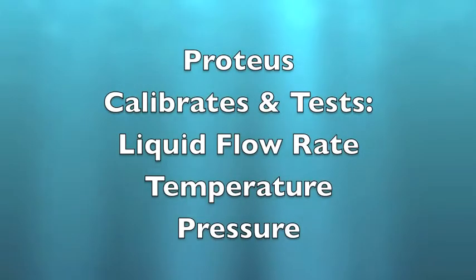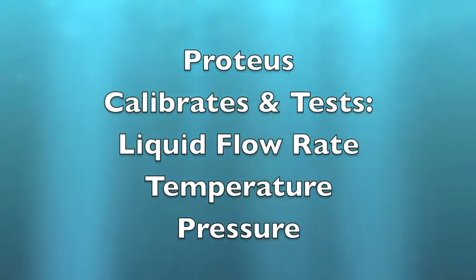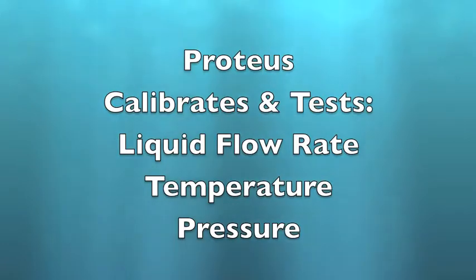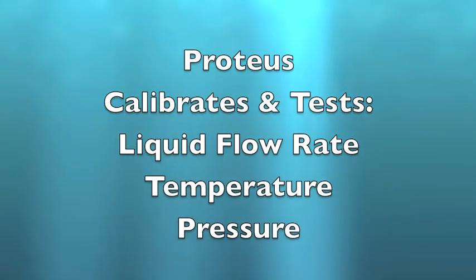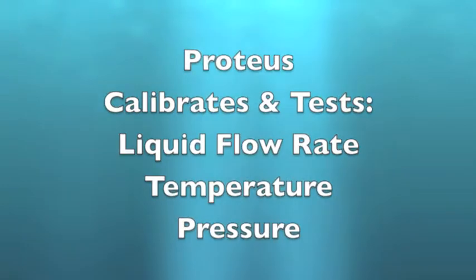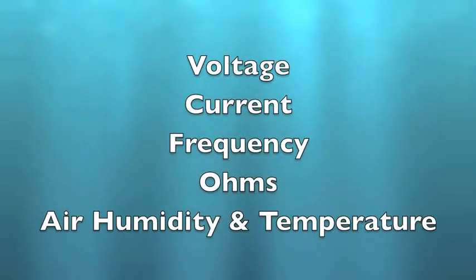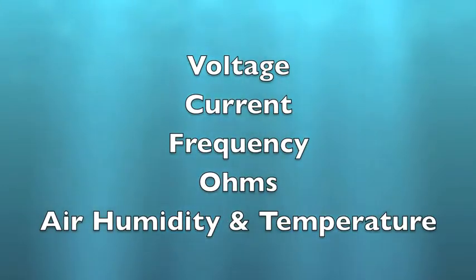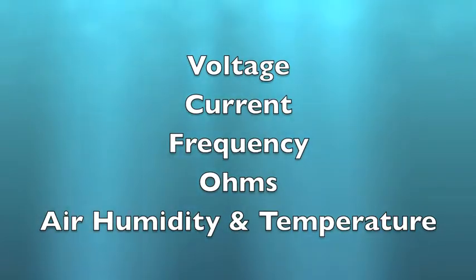Proteus must calculate measurement uncertainty for all of the things that it calibrates and tests: liquid flow rate, temperature, and pressure, as well as all other units measured in those calibrations — voltage, current, frequency, ohms, and air humidity.